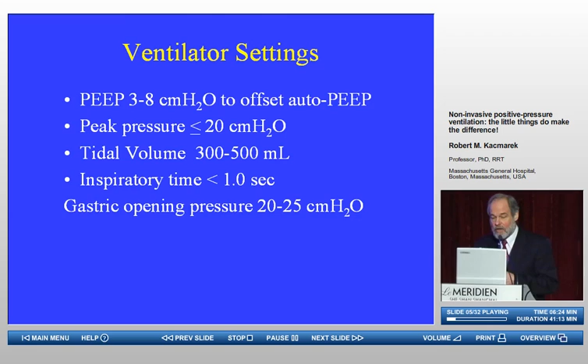And I try to emphasize the fact that these patients rarely are going to have lengthy inspiratory times. Most of them will ventilate with very rapid inspiratory times. And as you look at the response of the ventilator, as we'll talk about in a second, if inspiratory time is prolonged, we should look for a reason for that, because most likely the patient is not going to choose a ventilatory pattern with a 1.5 second or a 2-second inspiratory time. There may be a technical issue that is associated with why that inspiratory time is lengthened.